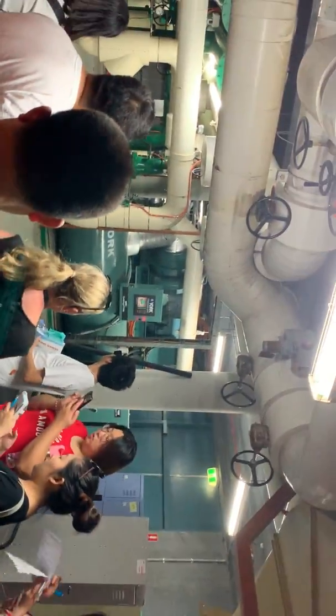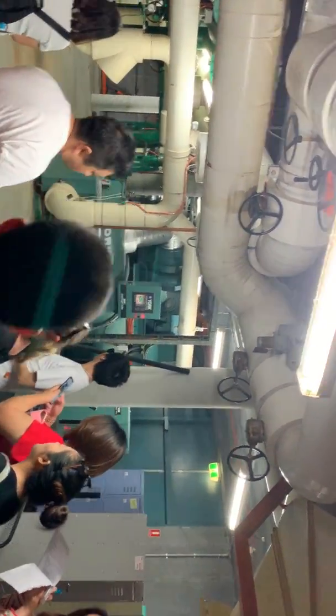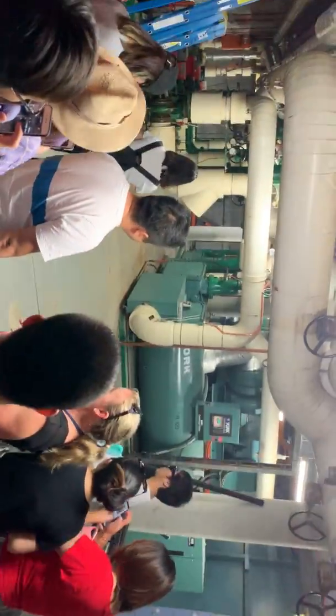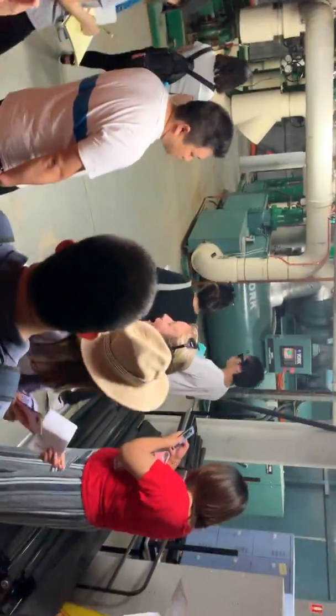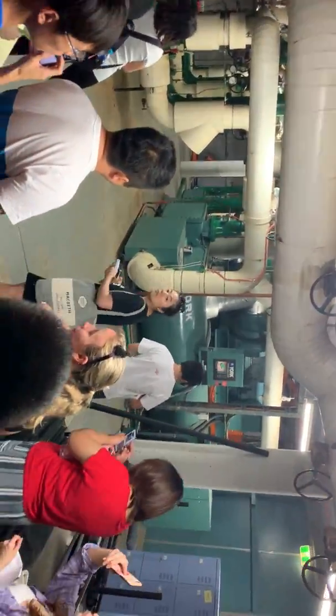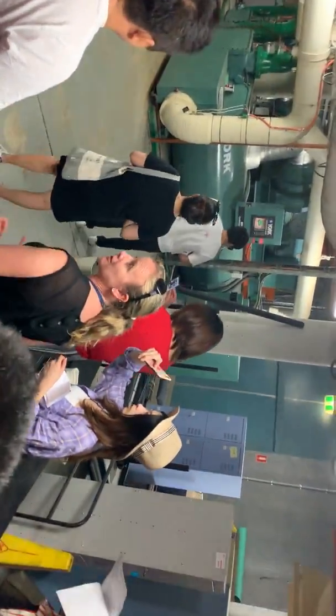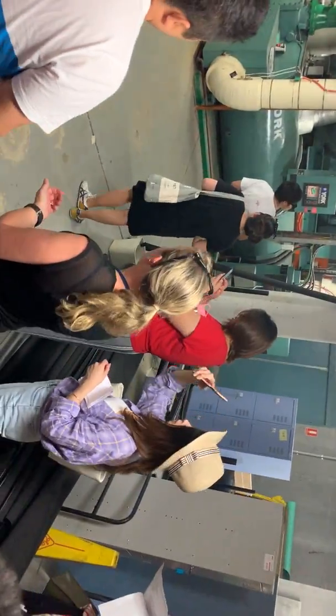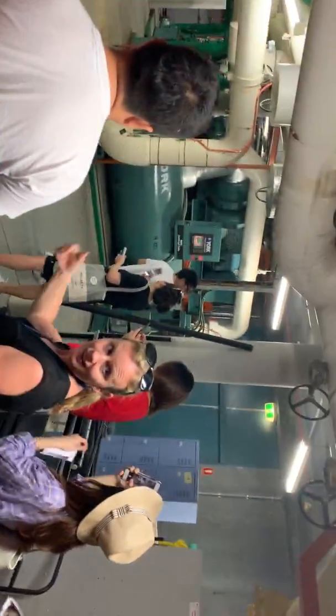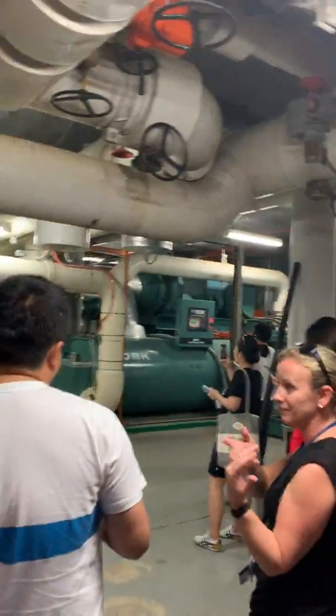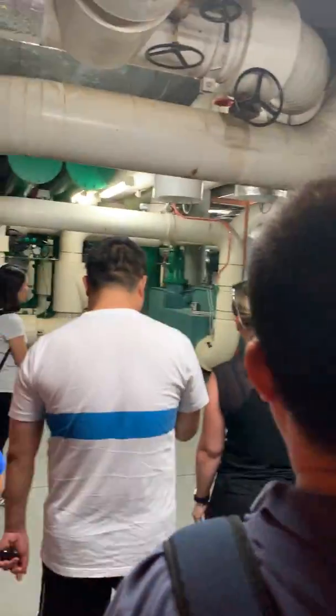You can see that there's 2 pipes connected to each chiller, so 2 white pipes. So outgoing, so the chilled water going off to the air handling unit at 5 degrees, and then the water that comes back from the air handling unit, which is usually around 10 degrees, so it can go back through that evaporator side of the chiller again, before it goes back to the air.